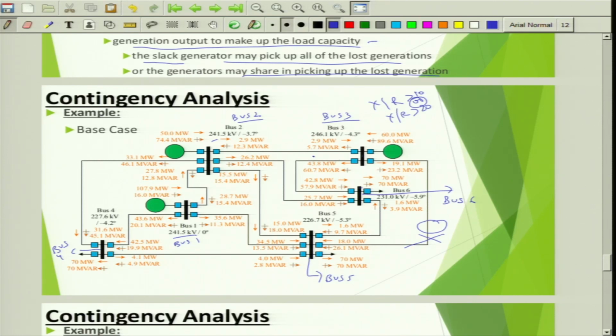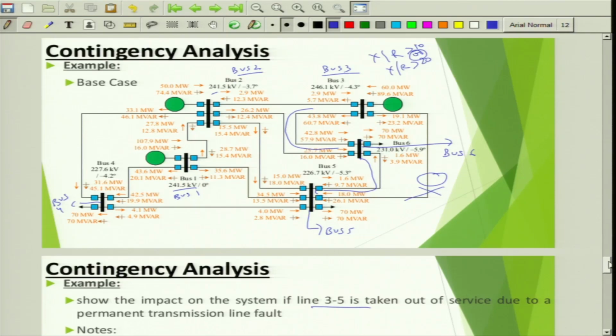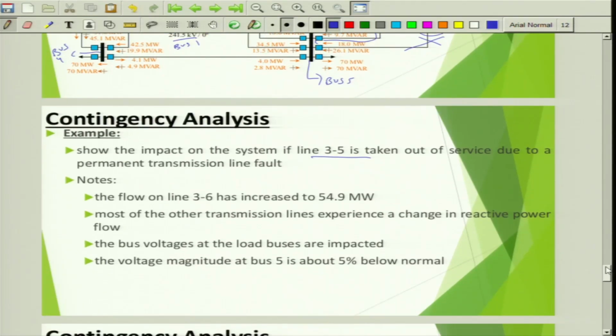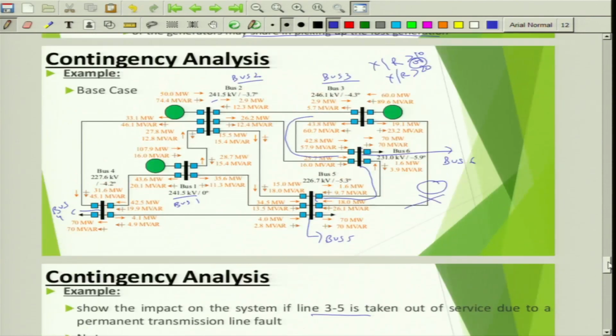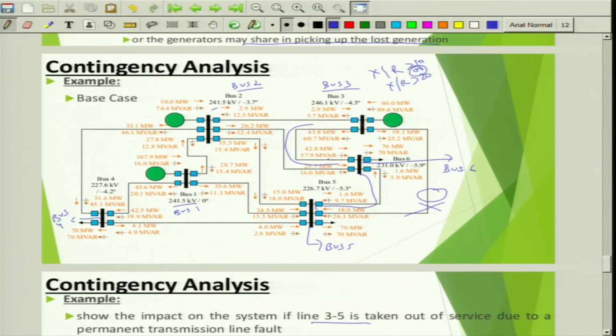Now there is a path still present. This line will have to carry the remaining power. So what is happening? The flow on line 3 to 6 has increased to 54.9 megawatt. That means there is a line between bus number 3 and 6, and there is an increase in power flow. I will show you that.